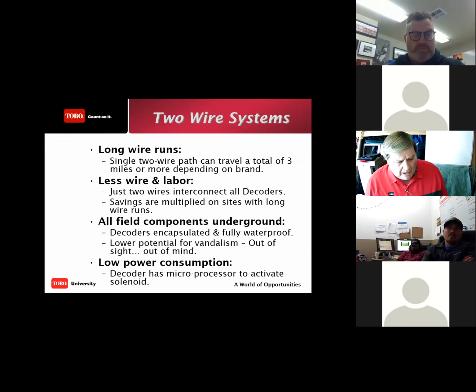You can have long wire runs, brand specific. Some will let you go up to 15,000 feet, which is a tremendous length of wire out there. But it's only a single 2-wire path. Less labor because you're only dealing with the 2-wire path. But there are some other things we're going to have to cover. Now, I like this because in high vandal prone areas, everything is underground except for the 1 clock. And that can be mounted in a building, in a utility closet, or wherever it's safe.